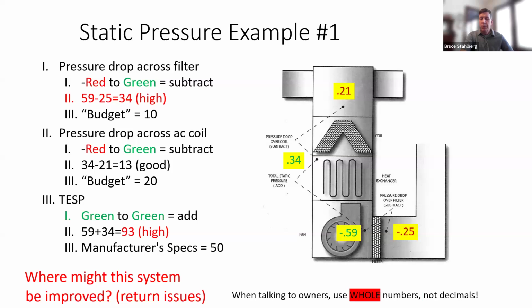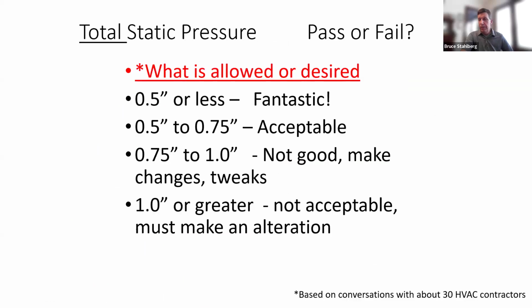what happens. Also, by the way, when you're talking to owners, do not talk about 0.21 inches of water column. It's always better to use whole numbers. So I would fail every, well, about 95% of the furnaces if I required 0.5 or less. But if we get there, that's really great. That's what the manufacturers want. If we, I allow it up to 0.75, I'm still okay with that. If we get above that, we need to start looking at changes, and anything above 1, we'll never pass it, and we need to make an acceptable alteration.